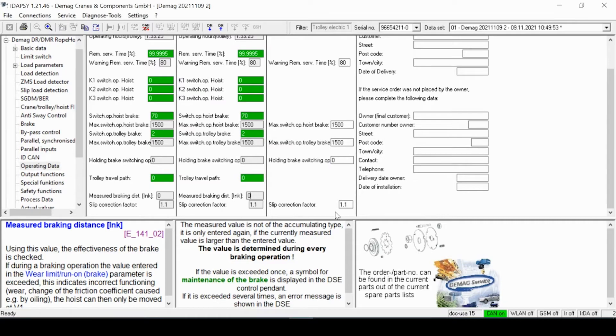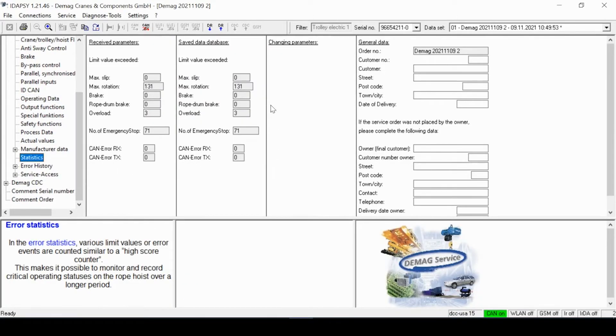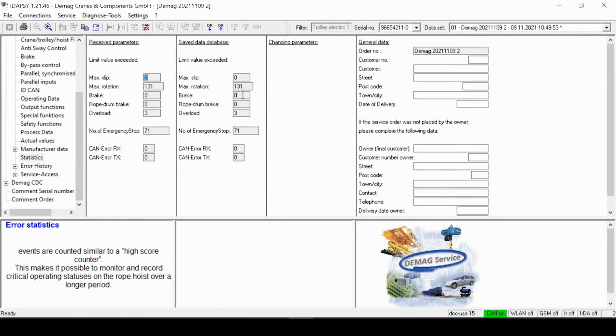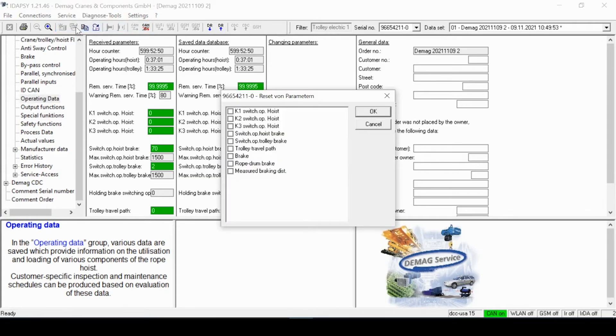Now I can check that in the statistics folder to make sure the counter value for brake has been zeroed. Going back to operating data, we'll look at the service reset menu one last time. The trolley travel path would be reset if I put on new trolley wheels or support rollers.